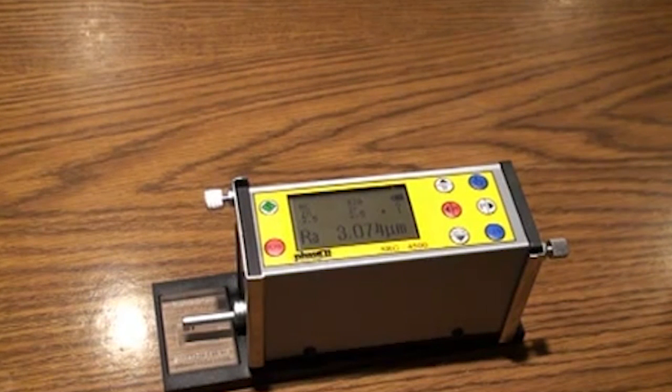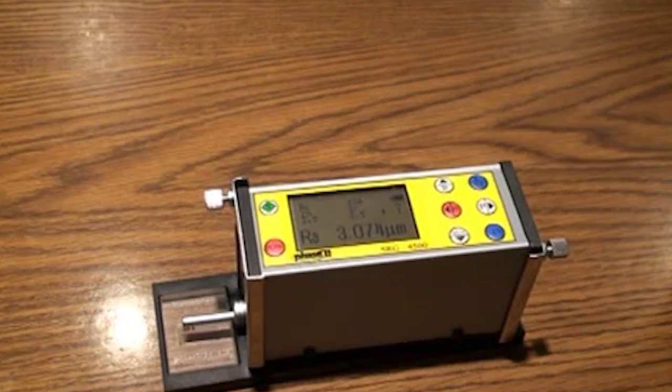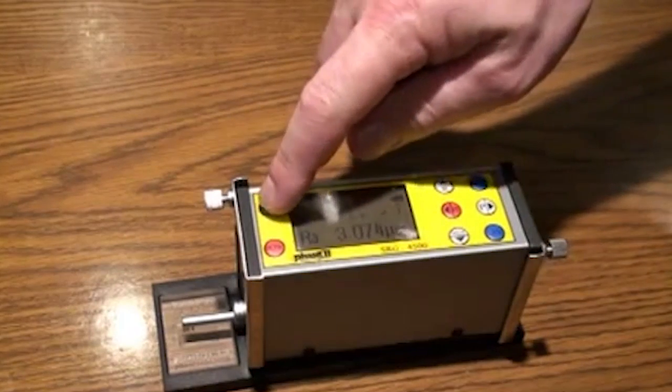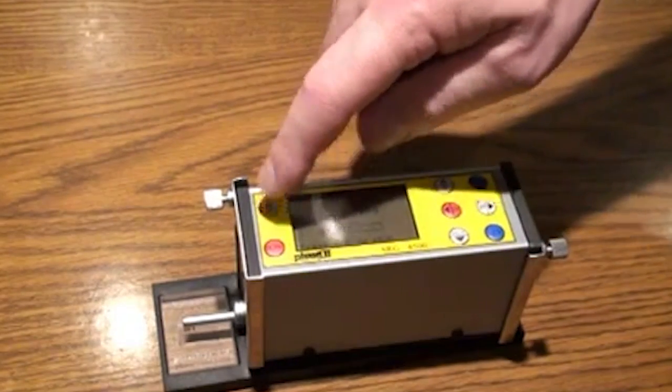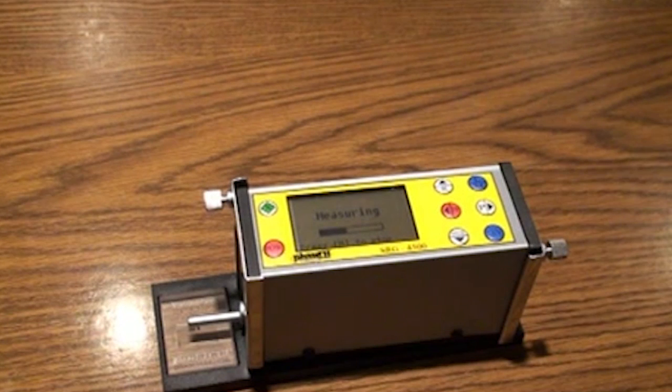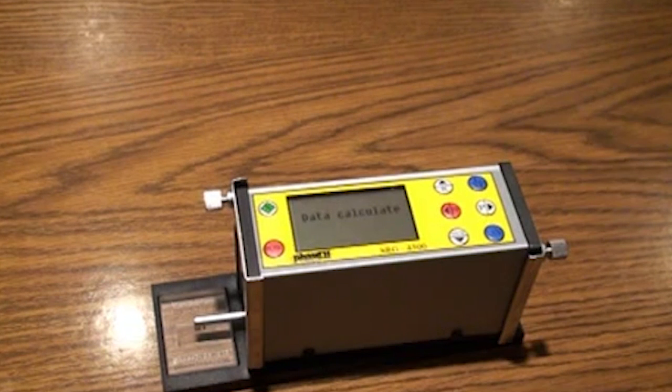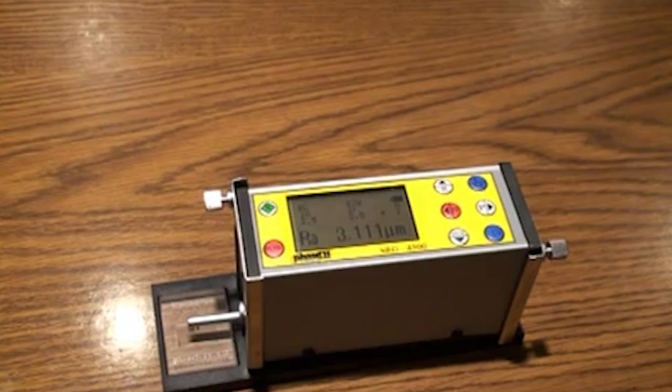Place the unit to test the supplied calibrated reference sample. Check the stylus level to make certain you are in zero range. Once back to the main measurement screen, press the S button on left to start the test. The unit will indicate that it is measuring. The value will show on screen in the roughness parameter you have chosen.